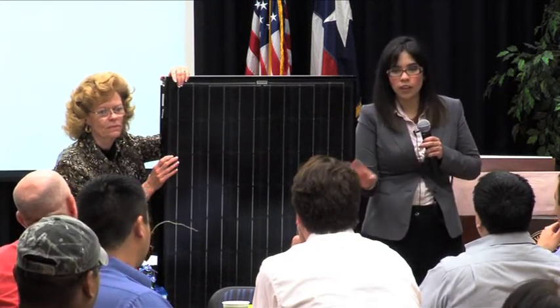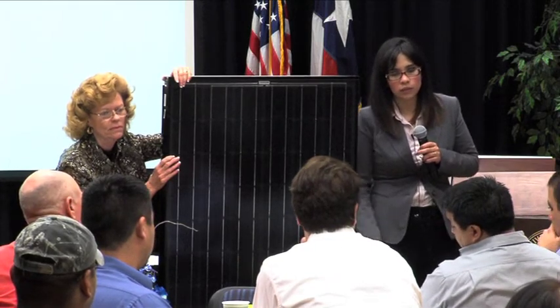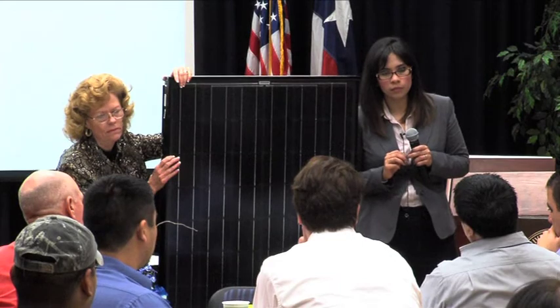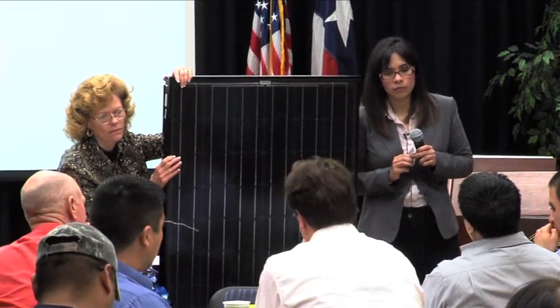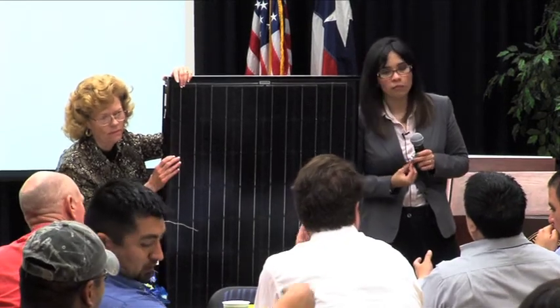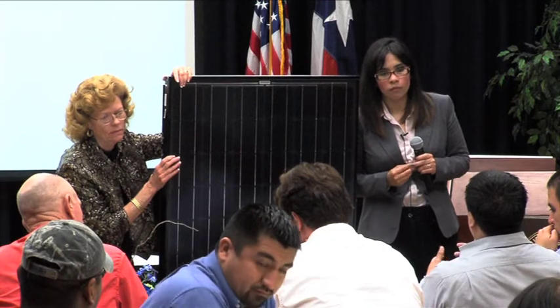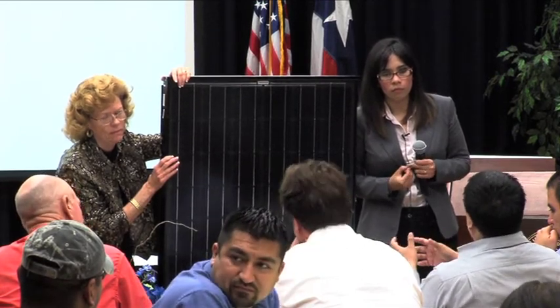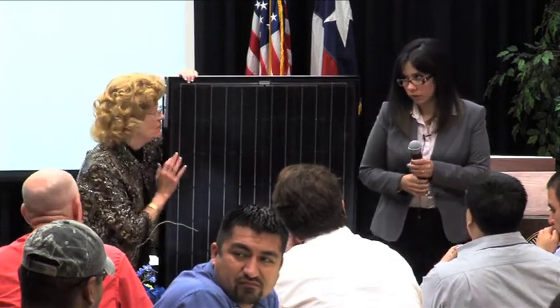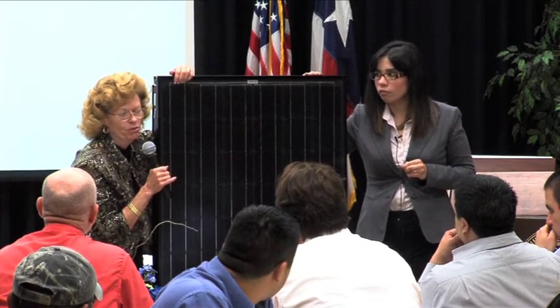An existing HVAC unit already has an energy management system and infrastructure in place. If it was LonWorks, BACnet, or IP based, you'd be able to tie your existing communication system into that unit and save on cabling infrastructure. When you order your rooftop unit solar ready, you can ask for a certified BACnet card or LAN card factory installed in the unit, or take your DDC controller off the old unit and put it on the new one, it ties right in. We are not a controls company, we tie into whatever system you have.